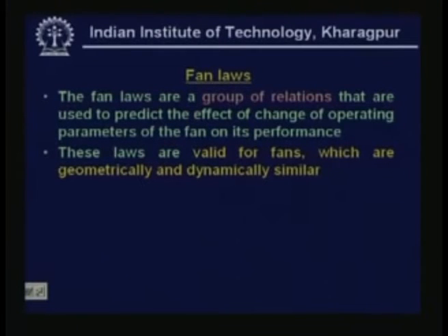However, you can use the fan laws to compare one forward curved blade fan with another forward curved blade fan of different size, maybe. This is what is known as geometrical similarity. Similarly, you also have to have dynamic similarity, that means the force ratios for these two fans have got to be the same. So, for geometrically and dynamically similar fans one can use the fan laws.